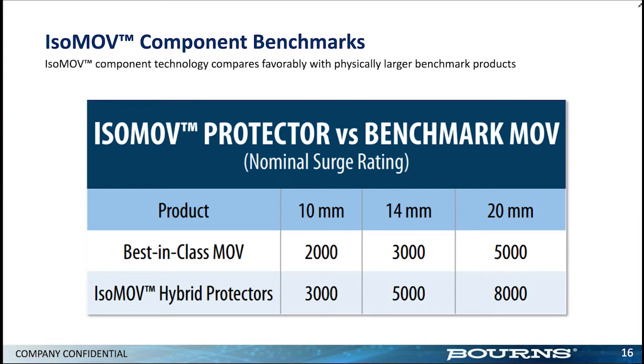And because they're so good, you have a couple options now. Let's look at the 14 millimeter. Well, let's look at the rows, best-in-class MOVs. Right now, in 10 millimeters, you can find 2 kA parts, 3 kA for 14 millimeter, 5 kA for 20 millimeter. But the IsoMOVs bump this up. So, like for a 14 millimeter part, you can keep the same part, swap out your MOV with an IsoMOV, and you've almost doubled your capacity, around 50% increase from 3 kA up to 5 kA without changing anything. Or you can move from a 14 millimeter normal MOV down to a 10 millimeter IsoMOV, give you the same protection, but now you're in a smaller package, so now you're saving some space.